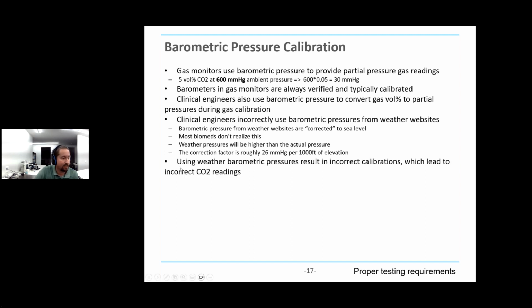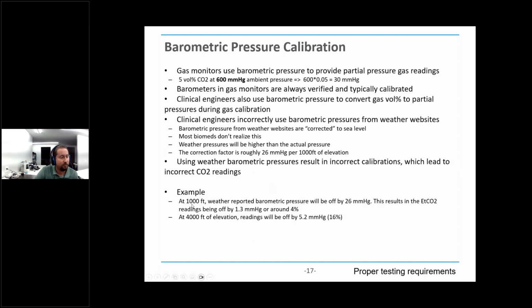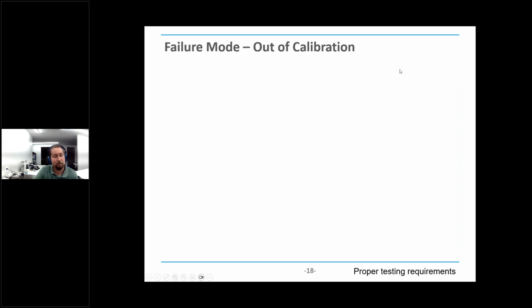So just as an example, if you're at 1,000 feet, you can be off by 4%. By the time you get to 4,000 feet, you're off by 16%. So it really is important to make sure you have a gauge of some kind to give you an accurate reading on site and not just rely on weather websites. I brought that up because that ties into the last failure mode I want to talk about, which is just being out of calibration. We've seen people use the wrong gas.